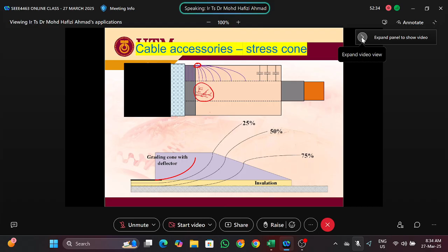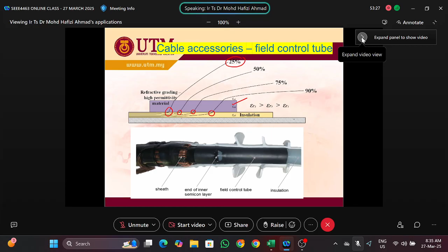So this is another field control type. We can use different permittivity so that it may guide the electric fields so they are not concentrated at just one point. This can be done using a refractive grading technique with high permittivity materials. We put another layer here or coating, and with the higher permittivity it may guide the electric field, concentrating 25% at this area, then 50%, 75%, and 90%. So it guides the electric field so that it's not concentrated at just one point. This is very important.